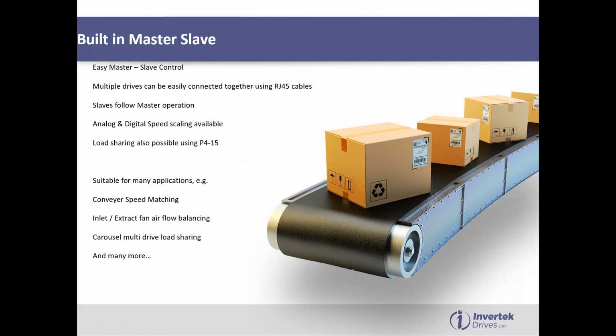We've also got built-in master slave, so you can connect multiple drives together. You have one master, and you can have several slaves if you need to. So if you've got an application like conveyors, where you have an in-feed conveyor which has to be feeding into a main conveyor, an out-feed conveyor, or a batching conveyor, we can actually scale the speeds of the different slaves on the system. So if you need a faster speed for the in-feed conveyor or a slower speed for the out-feed conveyor, that's easily done in the drives.